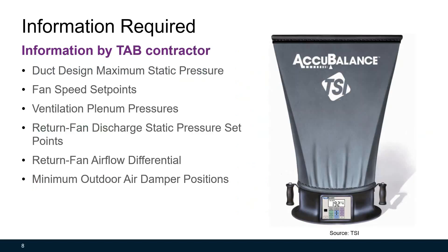Besides the design information, we also need to get some testing data from testing and balancing (TAB) contractors. Their job is to adjust the settings of installed HVAC equipment or air ducts so that pressures and airflows at the air handling unit or zone level are balanced and according to design. Such information includes duct design maximum static pressure, fan speed set points, ventilation plenum pressure, return fan discharge static pressure set points, return fan airflow differential, and minimum outdoor air damper positions.